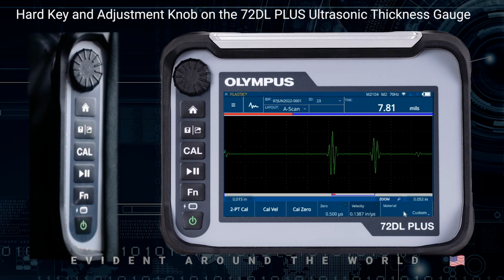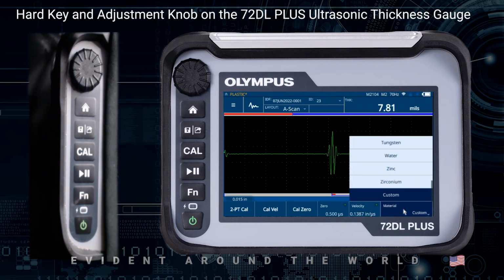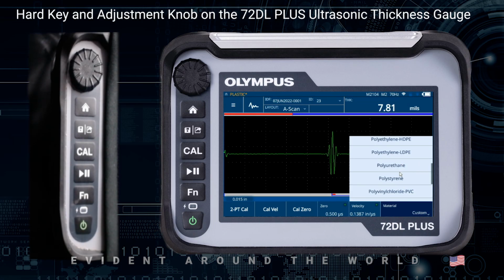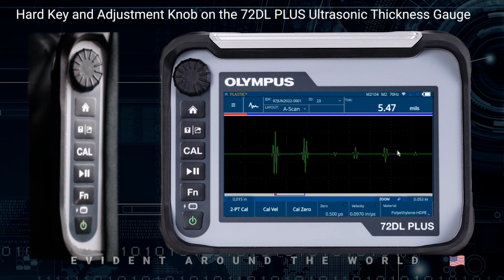I'm also allowed to select from the material list a material for my application. By scrolling up and down, it allows me to pick a material that's very similar to what I'm going to be working with. It's not a perfect solution, and should not be used in place of a real calibration, but it does get you a sound velocity that's in the ballpark of where you need to be. And then after you do your setup, you can do some fine tuning of the adjustment using one of the calibration functions. The calibration functions will be covered in a later video.